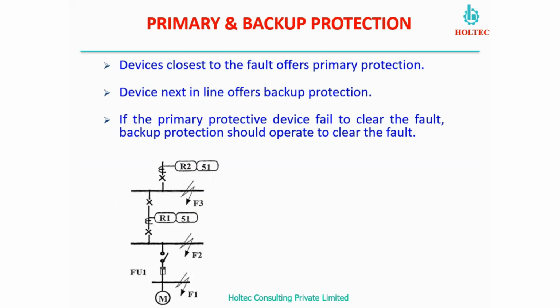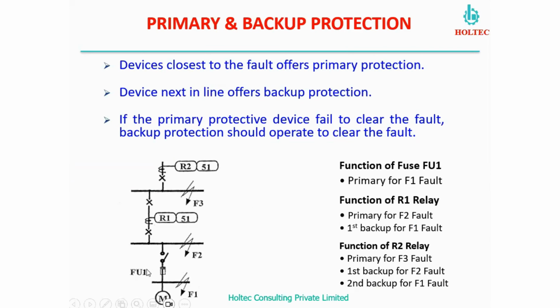To elaborate it further, let us check this example where we have three fault situations, F1, F2 and F3, and three devices: one fuse, FU1, and two relays, R1 and R2. So these are three devices and three fault locations. FU1 is the primary protection device for fault F1. This is the nearest one, so it will offer the primary protection for any fault F1 happening here. R1 is the primary protection for any fault in F2, but it also gives the backup protection for the fault F1. In the same way, R2 is the primary protection for fault F3, the first backup protection for F2, and the second backup protection for F1. In that way, the fault clearing process we decide and define.